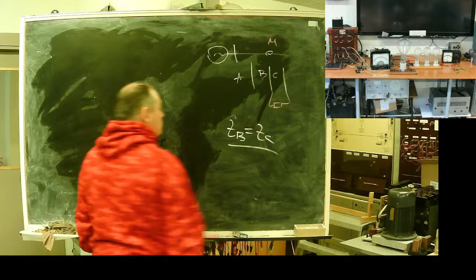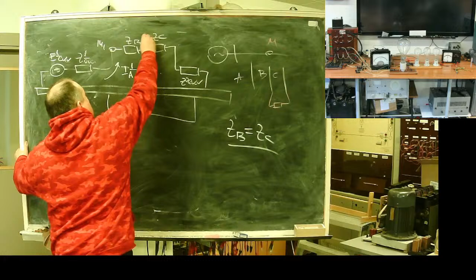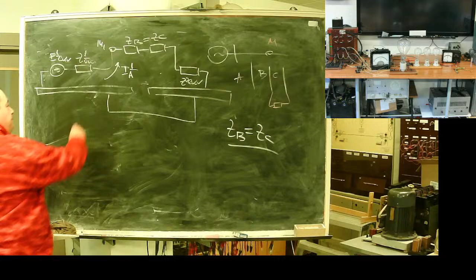For such a case, this will be your direct sequence equivalent, direct sequence EMF, M1, ZB, and the equivalent of the negative sequence. And the current here, again, is the A phase direct sequence. It's a kind of magic, but they should be equal, or this will produce a useless result. This is the classic line-to-line fault.